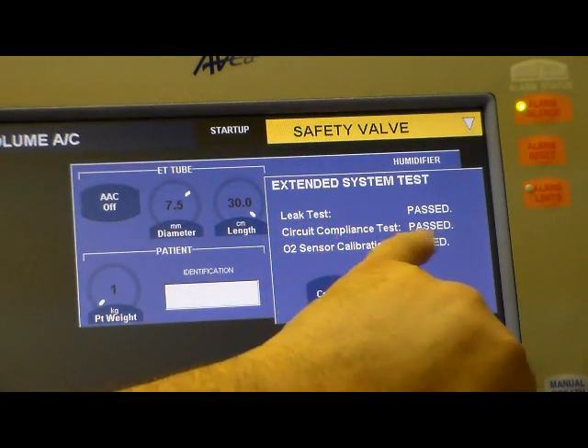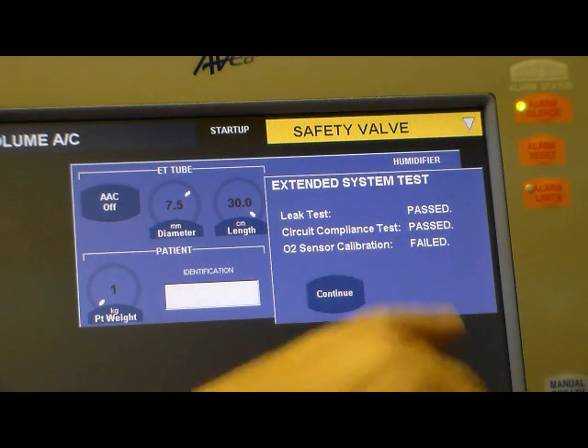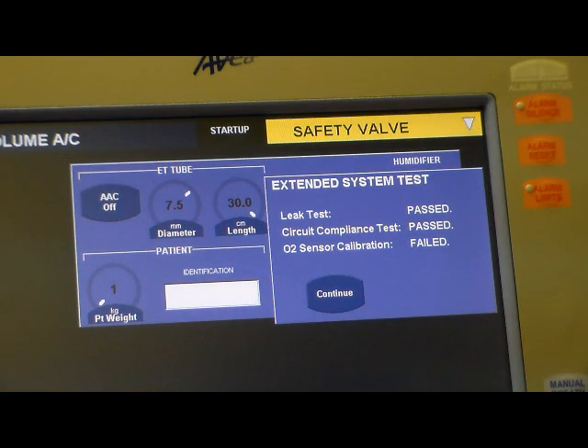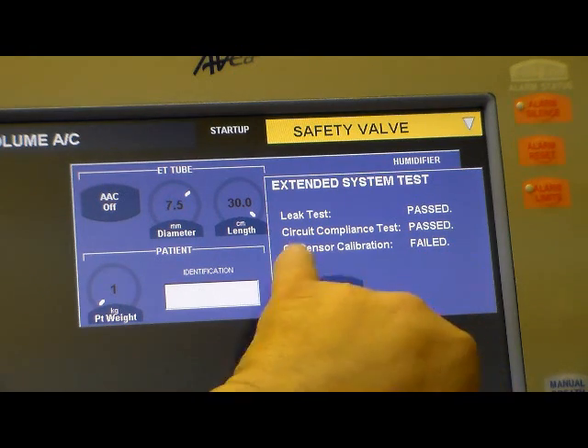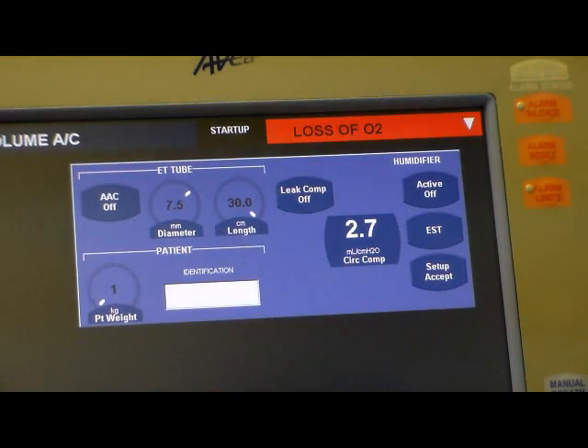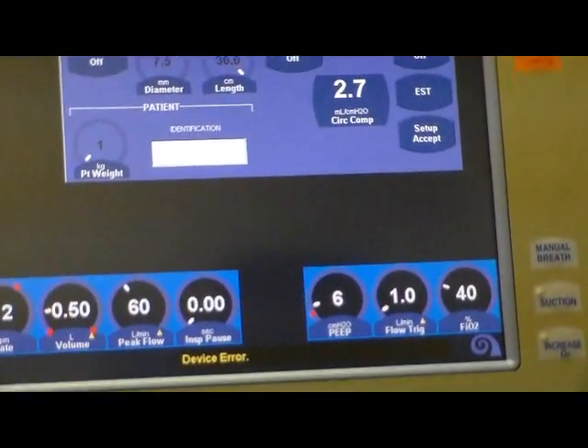We have passed the leak, passed the tubing compliance, but we did fail the oxygen sensor, and that's because we are not on gas supply right now. We're using the internal compressor to deliver the volume, so that's fine. We're not going to worry about the O2 sensor, so we're going to continue. And we have the information we want. We can then go down here to the respiratory rates. Let's move that down.